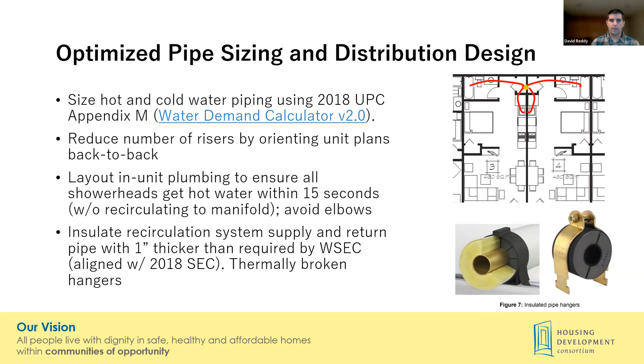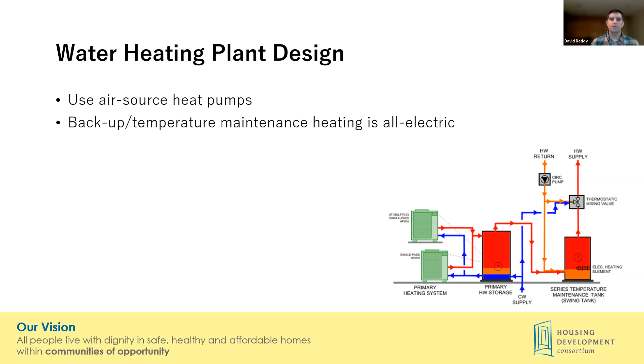Water heating plant design, we touch on in the guidelines, and our fundamental recommendation is to use air source heat pumps to reduce energy use. It's a huge measure, and we have the technology available today. And to do that with any kind of backup heating, use electricity, whether it's another heat pump or electric resistance. With a properly designed system and these optimizations of the distribution, there's not as much energy used for temperature maintenance, and therefore using electric resistance is a reasonable, lower maintenance, lower cost way to do it.